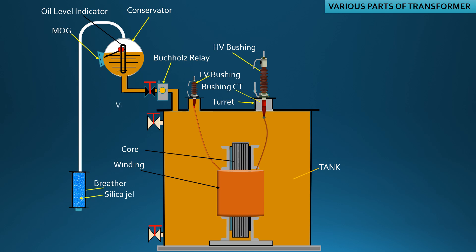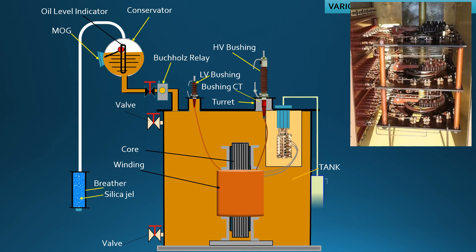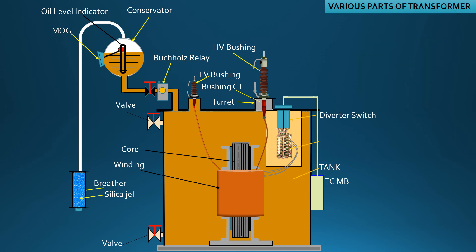These are inlet and outlet valves. It is OLTC, on-load tap changer, and DS and TC, diverter switch and tap changer. It works to control voltage of the load side to a desirable value by changing tap at HV side without shutting down the load or switching off the transformer.